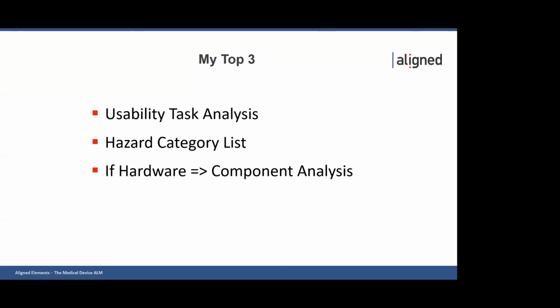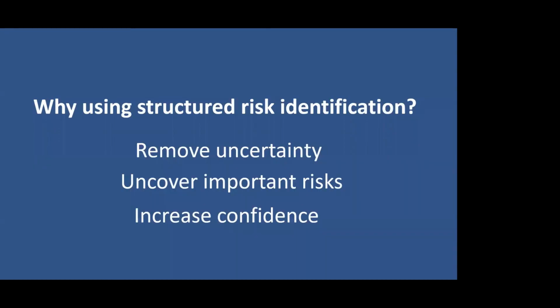And if you do hardware, it would be a crime not to do a component analysis, or what some people just call an FMEA. Basically ask yourself, given the thing that I have here in my hand, what happens if the different parts break or fail? So that would be my top 3 recommendations. But you know your device best. You know from your experience what kinds of risks you may have failed to identify, when you get this information from your post-market. So you might need what brings the best value to you.